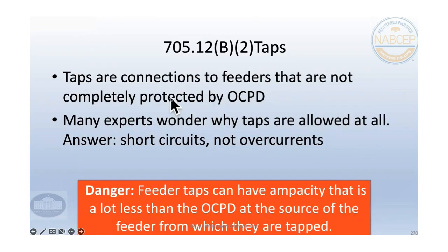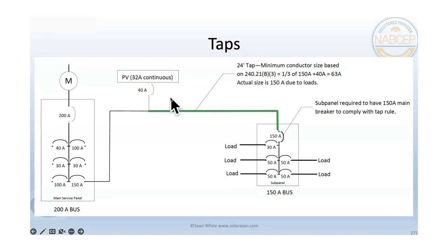So we did just cover taps a little bit, and so let's look at what we're dealing with here. So the 25-foot tap rule, they have that without solar. And so if you're tapping onto a conductor, you would have to apply that tap rule to this conductor where my mouse is, going to the inverter, and to this conductor going over here. But this conductor looks like it's pretty short. There's also a 10-foot tap rule. And so let's just see if I can explain what we're dealing with in this tap rule.